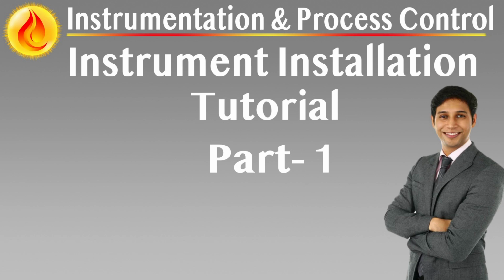Remote mounting, modular precision and separation of responsibilities. In remote mounting configurations, instrument process connections must terminate in a standardized lap joint interface to enable seamless integration with the tubing and manifold system. The preferred termination is a DN15 lap joint flange coupled with a lap joint tube adapter. This setup ensures mechanical robustness and standardization across diverse installations.